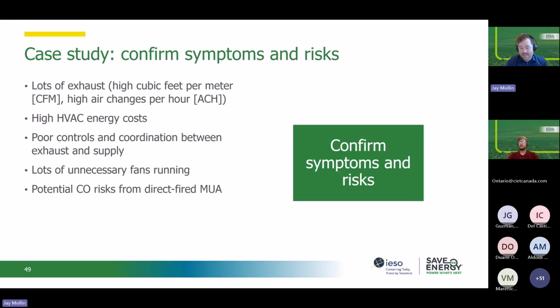That first step of confirming the symptoms and risks. So in Craig's facility, they've got a lot of exhaust, weld booths and different industrial processes happening. So high CFM air usage, high air changes per hour as a result of that. And because of that, very high HVAC energy costs. So natural gas in particular, but also electricity through the fans and everything else.